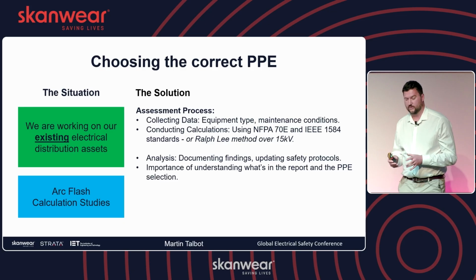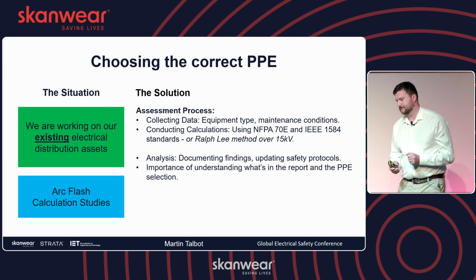I think it was Mark this morning who mentioned having a specification. And when you do this, it's really important to have that specification. So for example, ours is in substations that we completely control, we have a 40 cal limit for when you're opening up and proving dead, confirming dead within equipment. That's when the bomb suit's required. As soon as you've confirmed dead, you can take it off. So that 40 cal is really only worn for absolute minutes. And then within substations, we have a daily workwear.